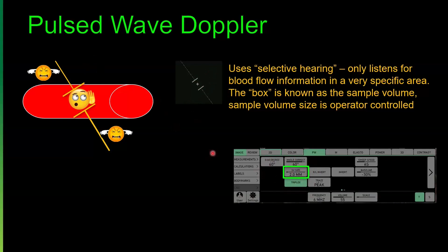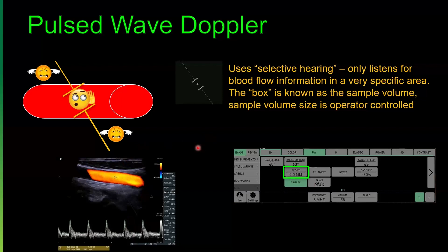And I can be very precise about velocity measurements and those types of things. And again, remember that's operator controlled. Somewhere on your system, you'll have a control that says what the sample volume size is. In this example, it's 2 millimeters, depending on your equipment and how big that will get. But then you'll get some sort of indicator on the screen that shows you right inside that box, or between those two lines, is where I'm listening, where I'm getting the information from. So when we look at this vessel over here, you can see the sample volume sitting right in there. So down here does not represent what's going on here or here or here, just where that sample volume is placed. But that's okay, because I'm using pulsed wave Doppler because I want to know what speed, direction, resistive indices, etc., are occurring in that particular spot.